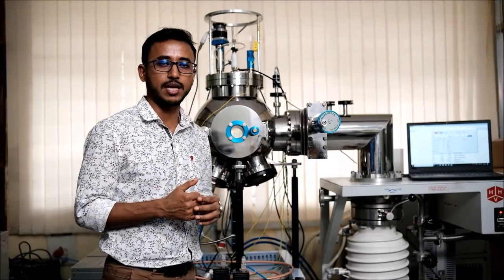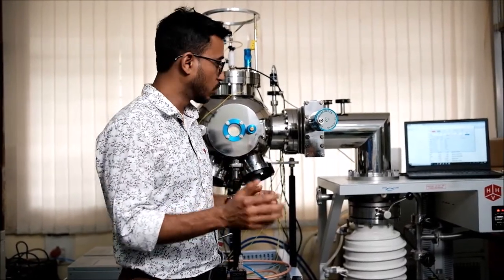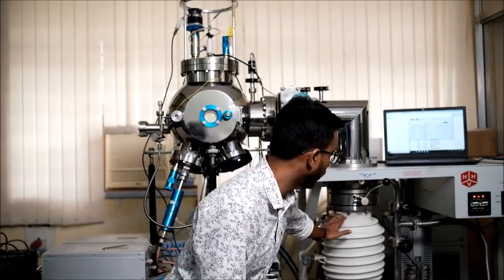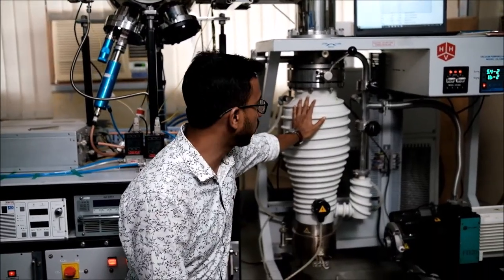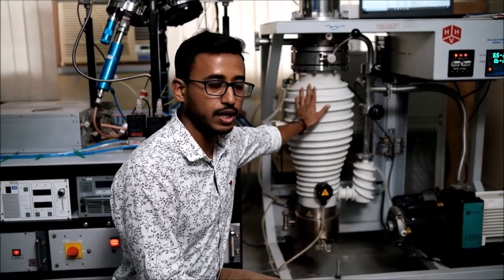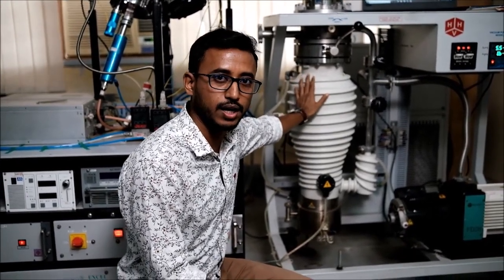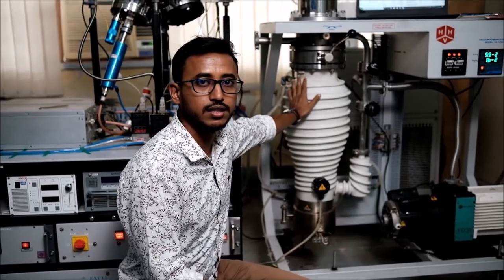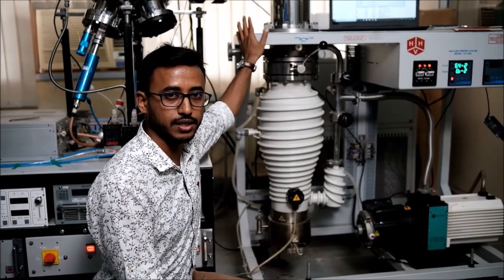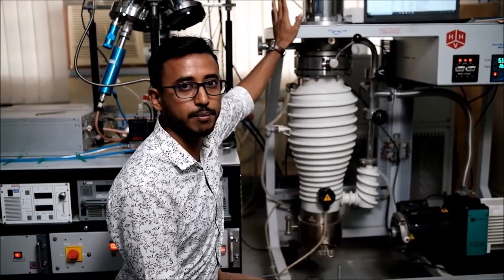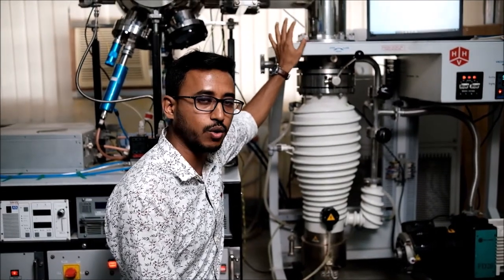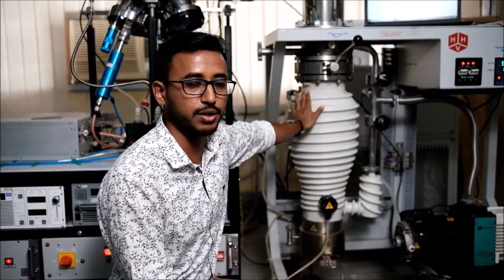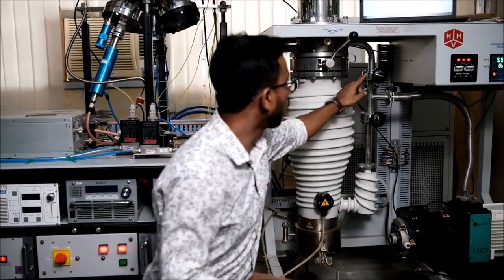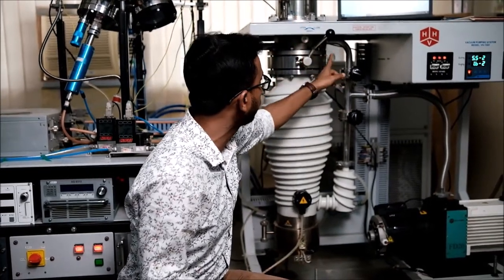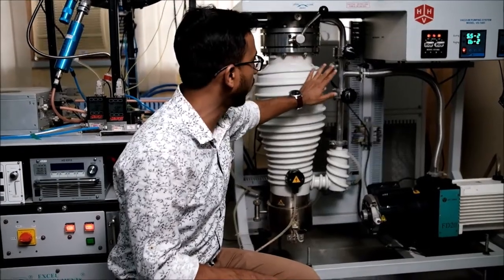I would also like to share some of the precautions we have to take when using the diffusion pump. As we know, we heat up the diffusion pump oil, and we should not heat it up without evacuating the chamber. Also, after heating up the diffusion pump oil, we should not connect the diffusion pump directly to atmospheric pressure. That means only after evacuating the chamber to 10 to the power minus 3 millibar pressure can we connect this chamber to the diffusion pump chamber. And also we should not open the roughing valve and the vacuum valve at the same time. Then the gas from the chamber can directly come to the diffusion pump chamber. So we should avoid this.